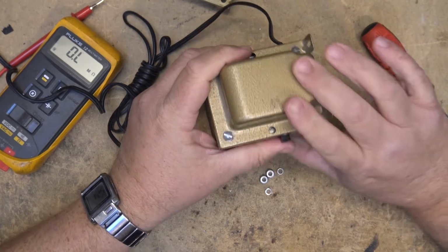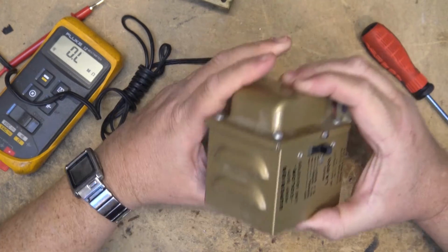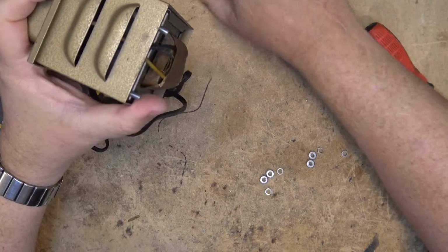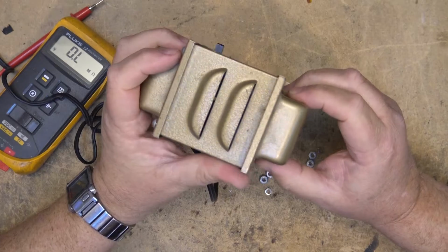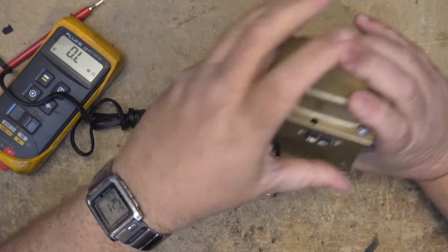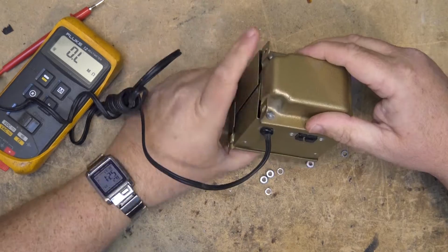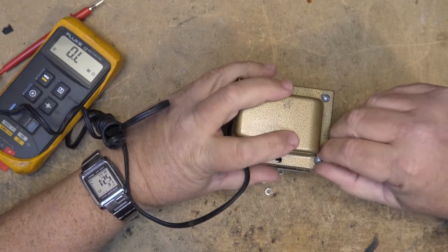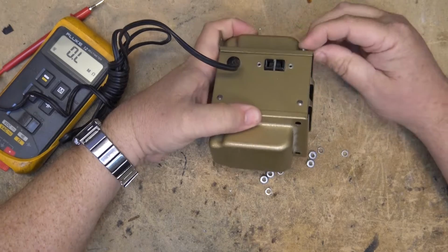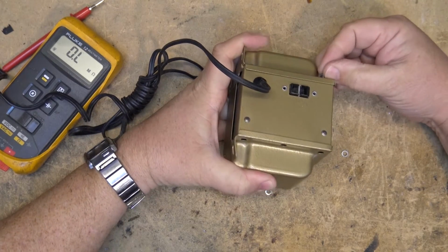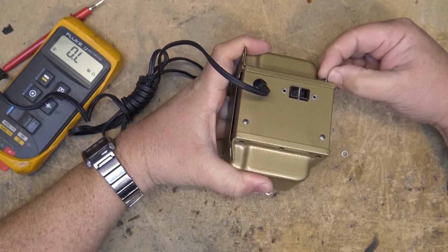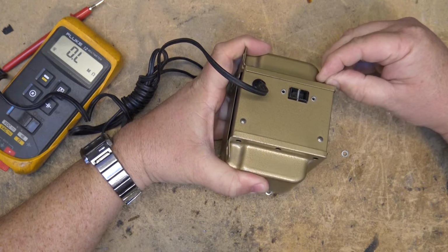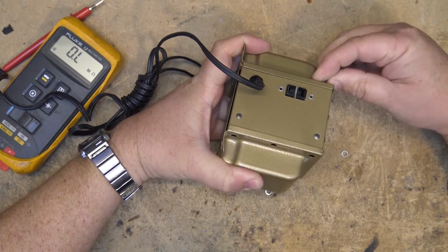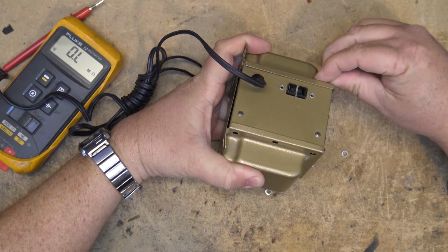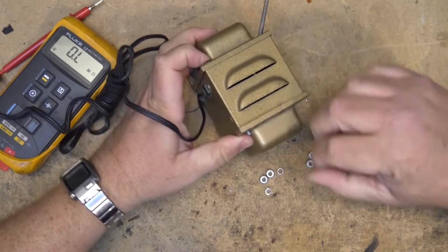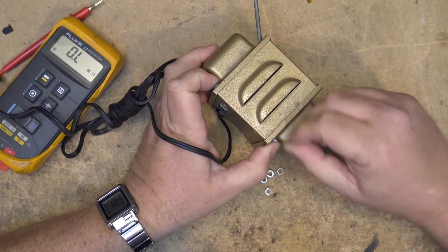I wanted to do this video because I didn't know whether this was isolated or not. I've had people tell me, oh, just use one of those line booster things, because that's an isolation transformer, and I didn't think it was going to do anything. I was pretty sure it wasn't an isolation transformer, but until we actually measure it and verify that, you can't say, right? So now we can say with certainty that this unit is not an isolation transformer. It cannot be used as one. If someone tries to pawn one of these things off to you as an isolation transformer, now you know they're not. You don't have any safety whatsoever.